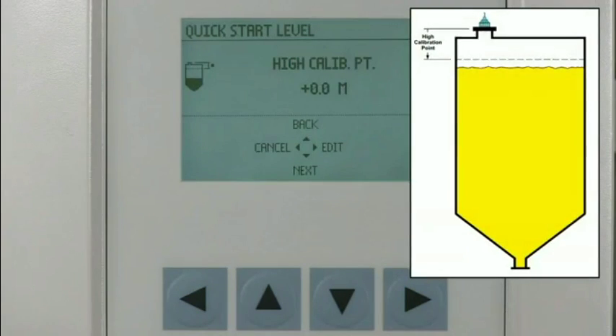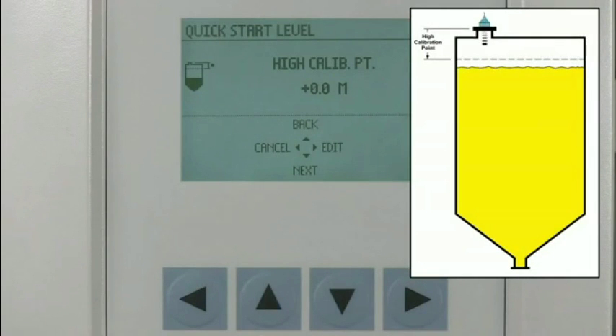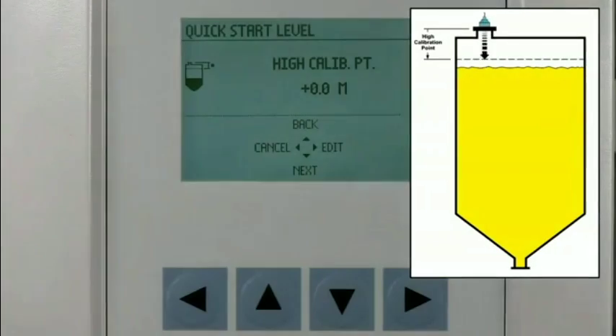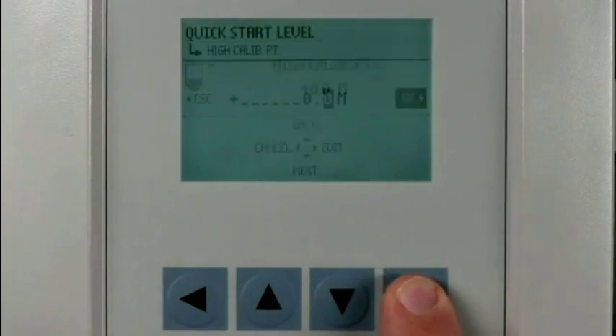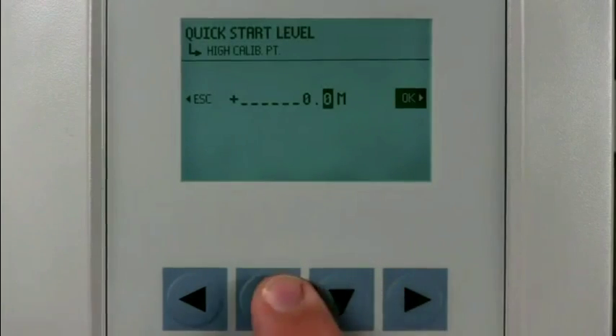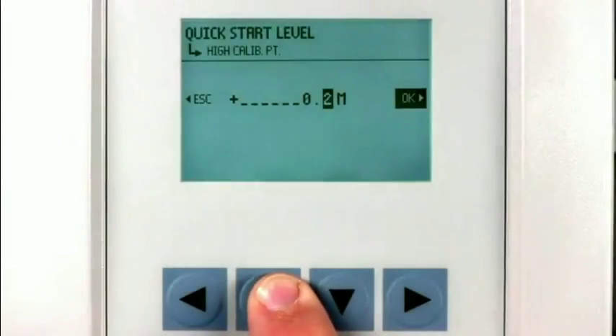The high calibration point is the distance from the transducer face to the highest point the material level will reach under normal operating conditions. We will enter a value of 0.5 meters in this parameter.